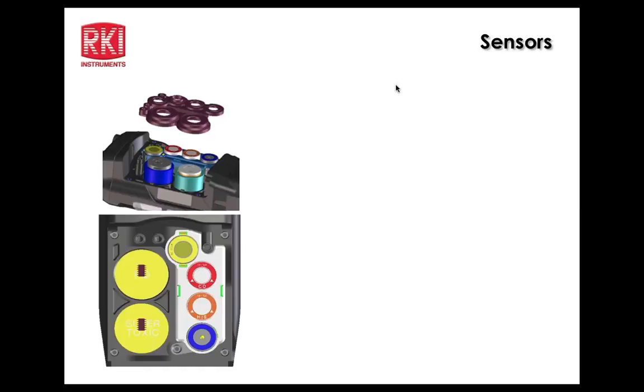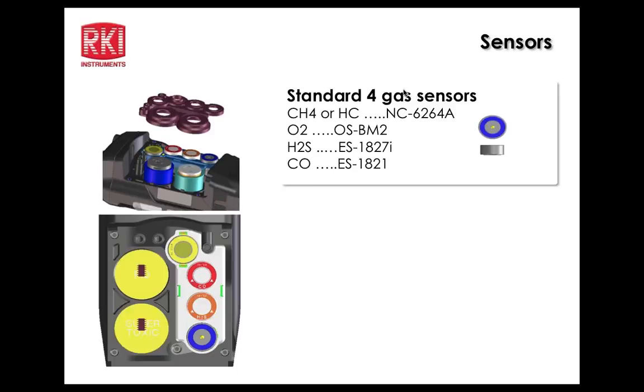When the PID is being used, it has to go in that first slot at the top, or that first sensor well. If the PID is not being used, then all the other sensors can go in either one. The unit does have the intelligence to properly identify and locate each sensor that's being used. So the PID, having the ability to monitor for low ppm levels of hydrocarbons where absorption could be an issue, that has to be first in the flow path, basically. So that's why it's important that it be located where it is.